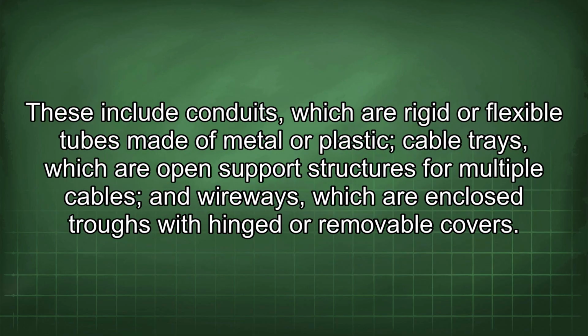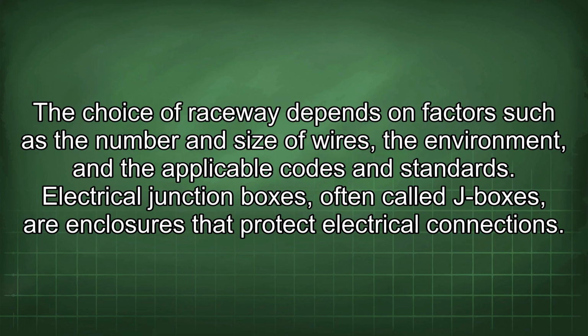These include conduits, which are rigid or flexible tubes made of metal or plastic; cable trays, which are open support structures for multiple cables; and wireways, which are enclosed troughs with hinged or removable covers. The choice of raceway depends on factors such as the number and size of wires, the environment, and the applicable codes and standards.